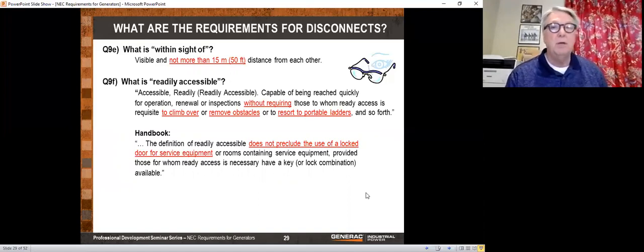In the handbook, it clarifies that the definition of readily accessible does not preclude the use of a locked door for service equipment. So if you have a locked door, it is still readily accessible to those with a key.